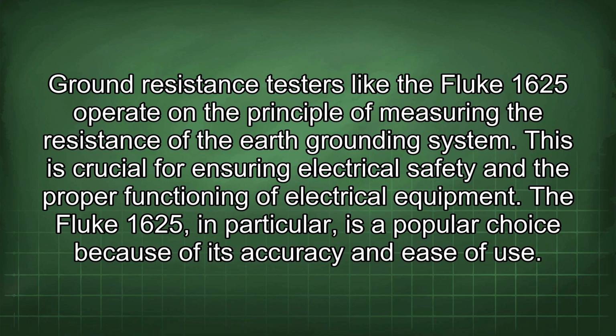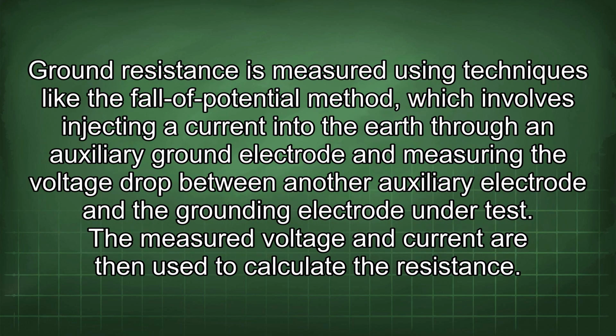Ground resistance testers like the Fluke 1625 operate on the principle of measuring the resistance of the earth grounding system. This is crucial for ensuring electrical safety and the proper functioning of electrical equipment. The Fluke 1625, in particular, is a popular choice because of its accuracy and ease of use. Ground resistance is measured using techniques like the fall of potential method, which involves injecting a current into the earth through an auxiliary ground electrode and measuring the voltage drop between another auxiliary electrode and the grounding electrode under test. The measured voltage and current are then used to calculate the resistance.